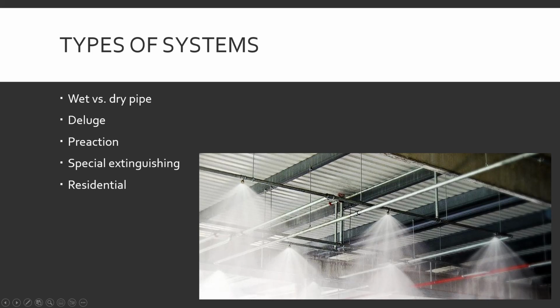The dry system at this valve will have a big opening on the valve. Like, pretty big. The water side will have a smaller opening, like half or quarter size. Guesstimating, but you get the idea. That is so if there's 60 psi here, because of pressure over square inches kind of thing, like 15 psi of air can keep 60 psi of water held in check. This is just easier to maintain in the system than 70 psi of air for 60 psi of water. You can do more with less.